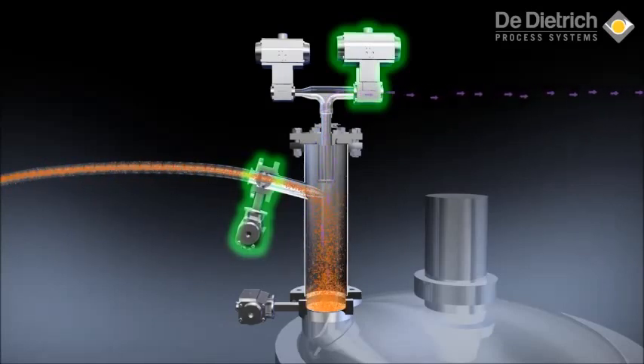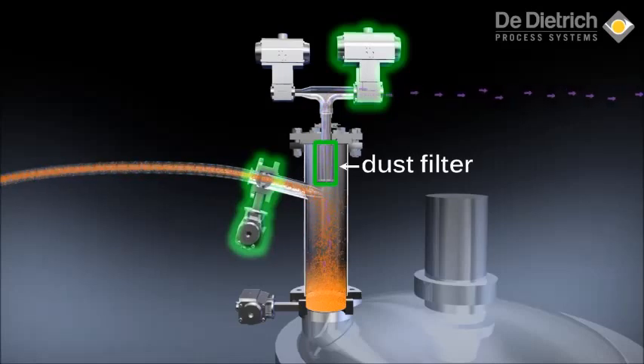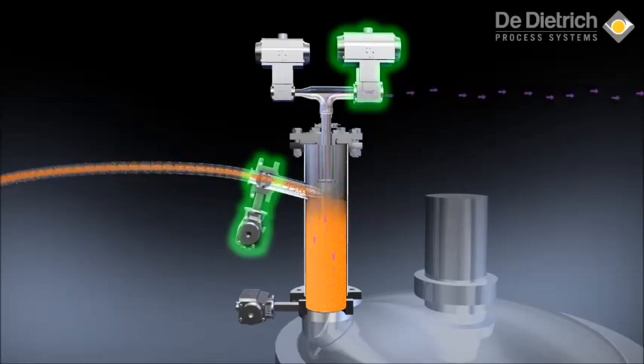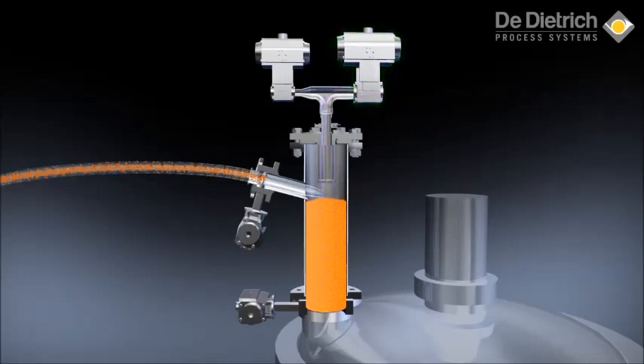Entrained gas is evacuated through the internal dust filter element, and the solids are retained inside the body. When the preset transfer time has elapsed, the powder inlet valve closes. A brief delay allows residual air to be evacuated, then the vacuum isolation valve closes.